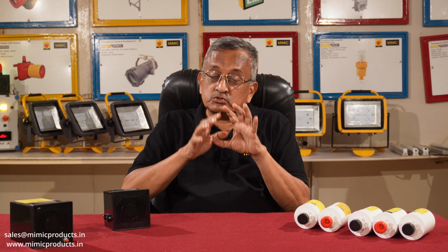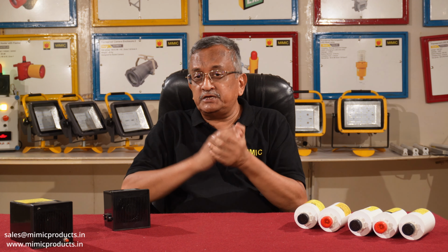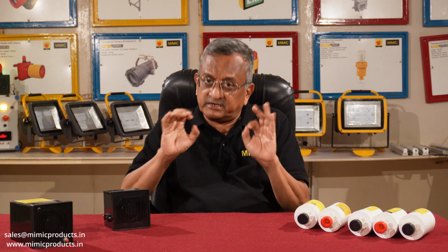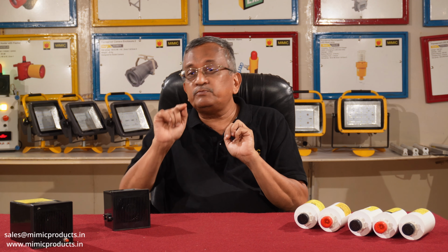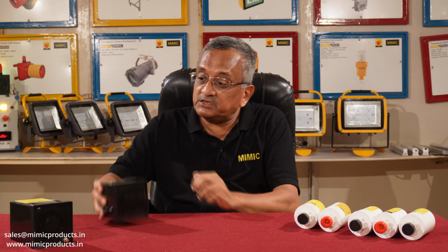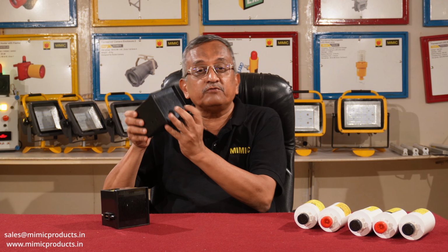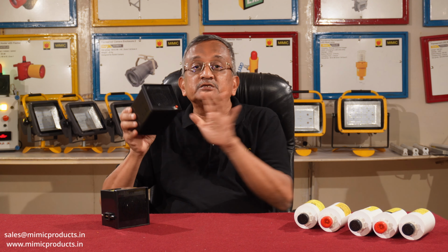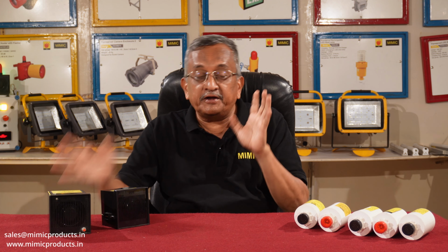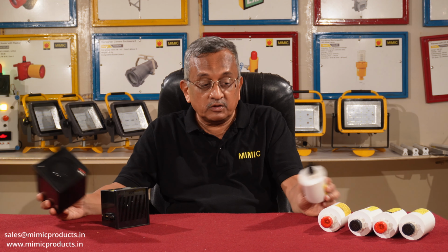That means when the hooter sounds, the operator comes over there, he knows the fault, and he says, yes, I accepted, I accept that the fault is there, but the sound has to be closed. So there are push buttons given on the front side. When the push button is pressed, the sound stops, but the light remains flashing till the fault is there. So these are called cancellation type hooters. Both types of hooters are available in 22.5 as well as in 92 by 92 cutout.